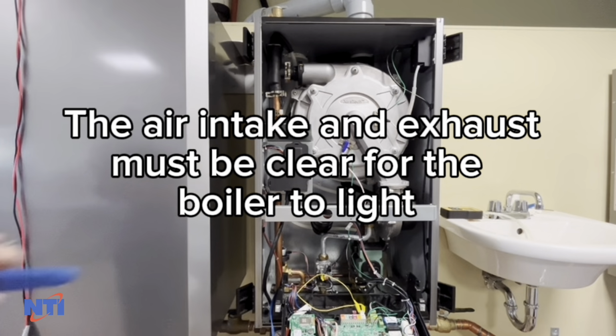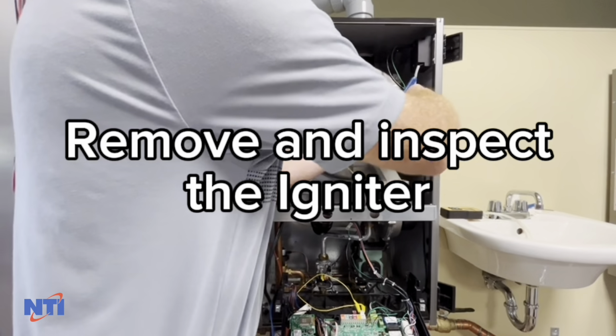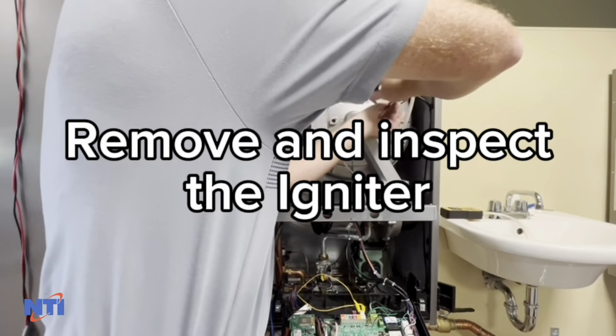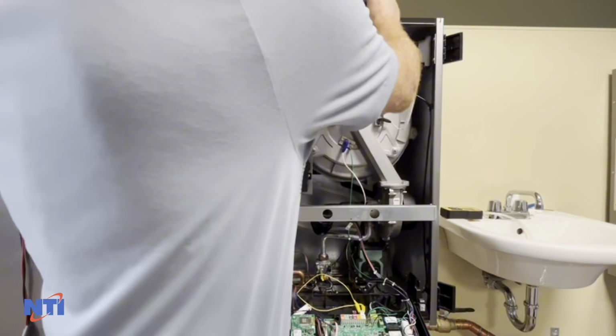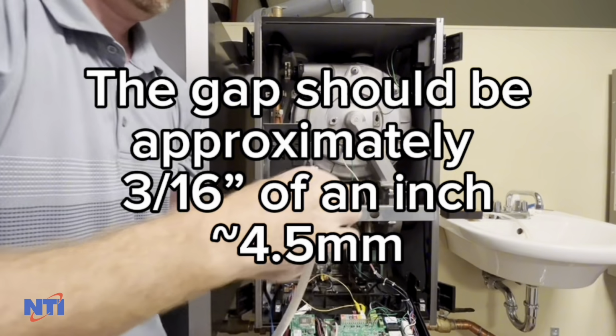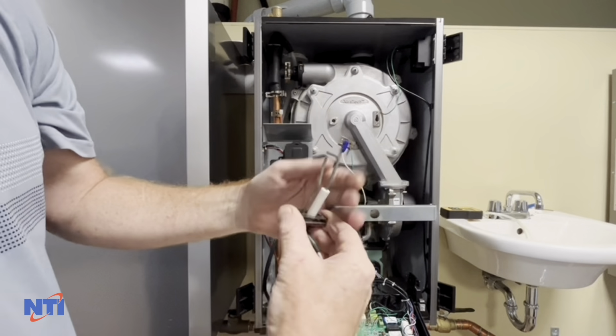Remove and inspect the igniter. You're looking for cracks or excessive warping. The gap should be approximately 3/16 of an inch. This igniter is in good condition and can be reused.